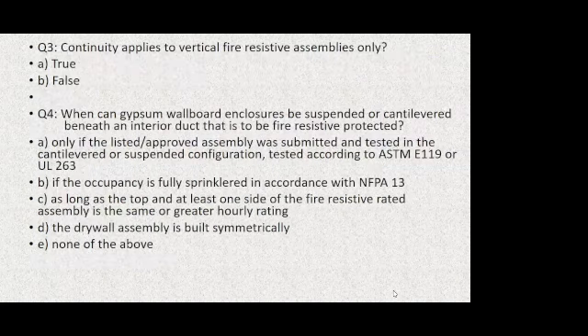Question 3, continuity applies to vertical fire resistance only. We don't need to worry about it when it comes to horizontal fire resistance. And then finally, question 4, can gypsum wallboard enclosures be suspended or cantilevered beneath an interior horizontal duct that needs to be fire rated?